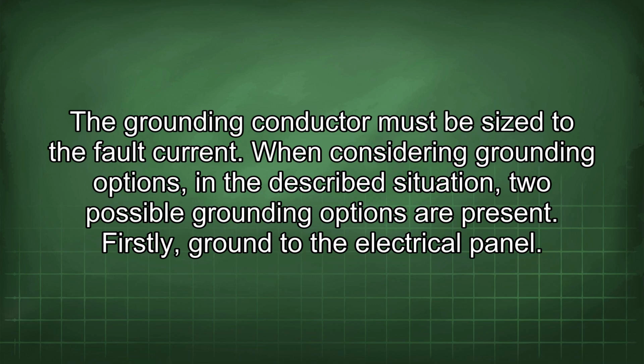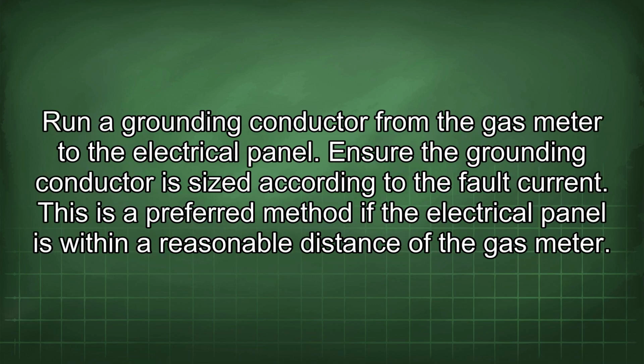When considering grounding options, in the described situation, two possible grounding options are present. Firstly, ground to the electrical panel. Run a grounding conductor from the gas meter to the electrical panel. Ensure the grounding conductor is sized according to the fault current. This is a preferred method if the electrical panel is within a reasonable distance of the gas meter.